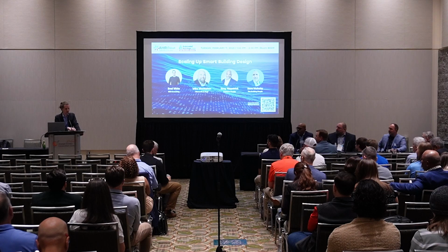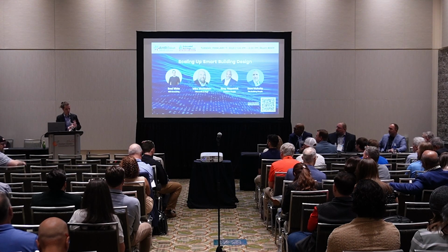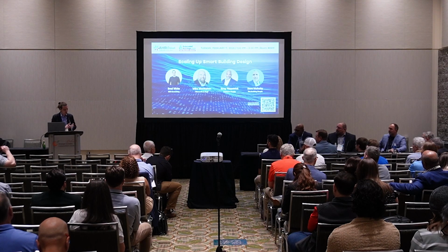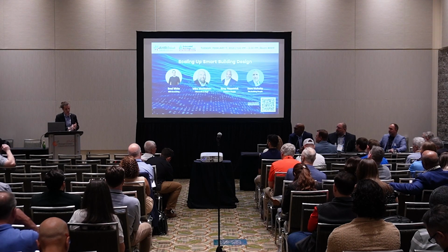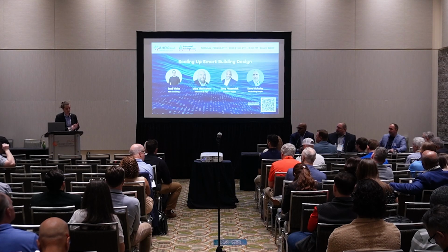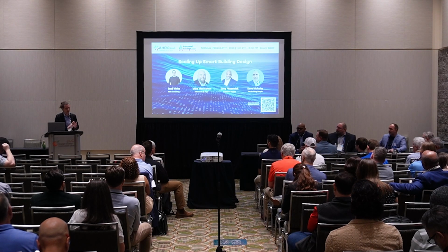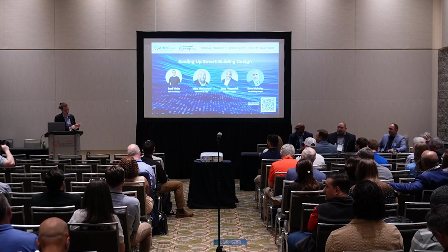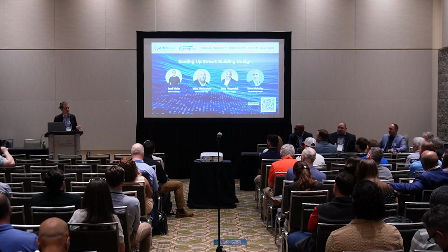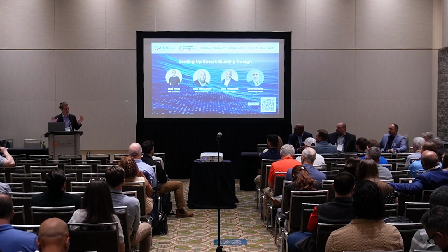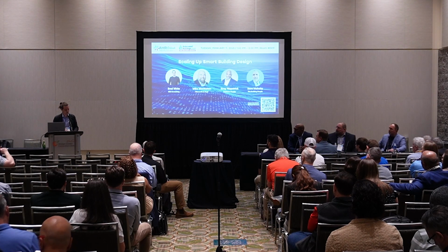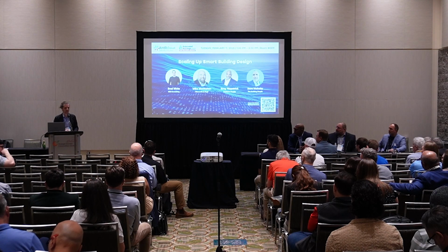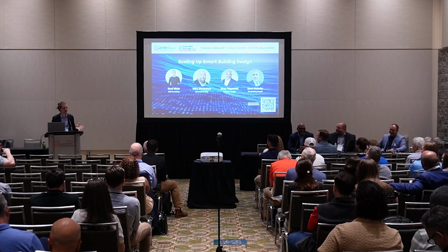But here we are, I don't know how many hundreds of millions of dollars this project was, but the fact that the controls could be completely overlooked. We have a client who is not following their own control standard and has no interest in following their own control standard, is faced with a legacy situation where they're going to be stuck with one operator dealing with two completely different control systems that are not going to talk to each other because nobody thought about integration. I don't want to use the term dumpster fire loosely, but that's kind of what it is.